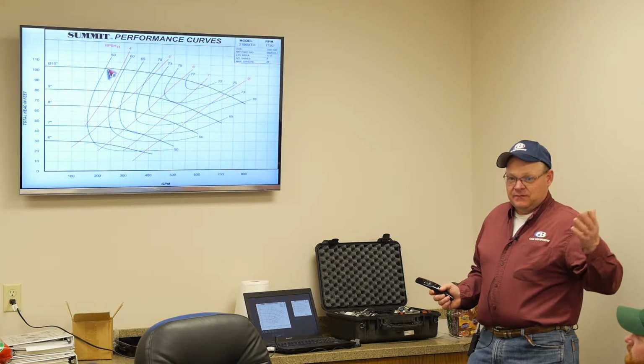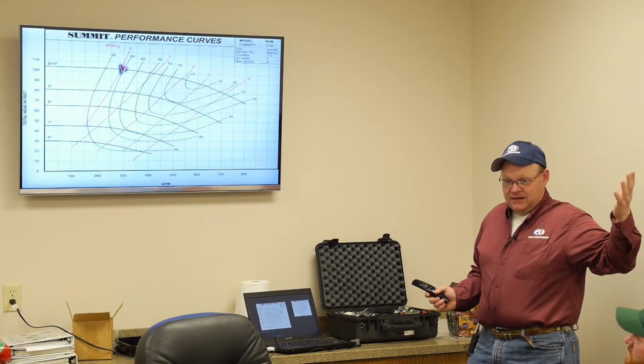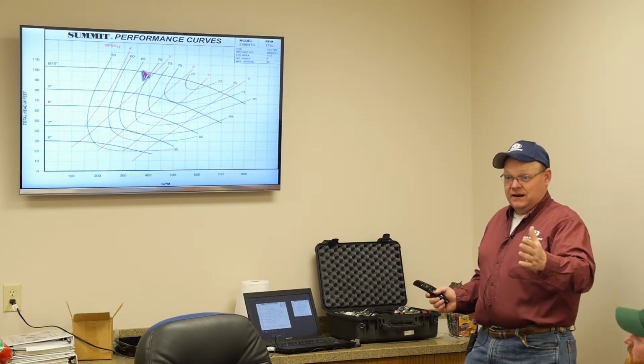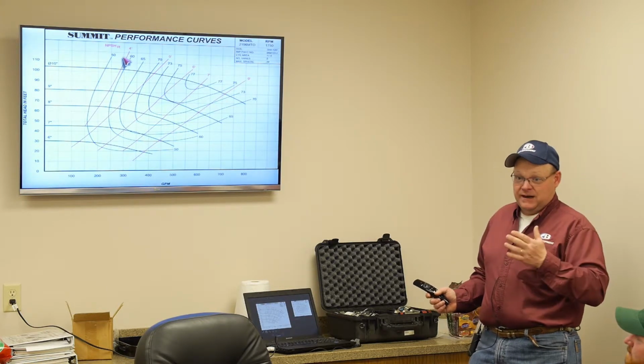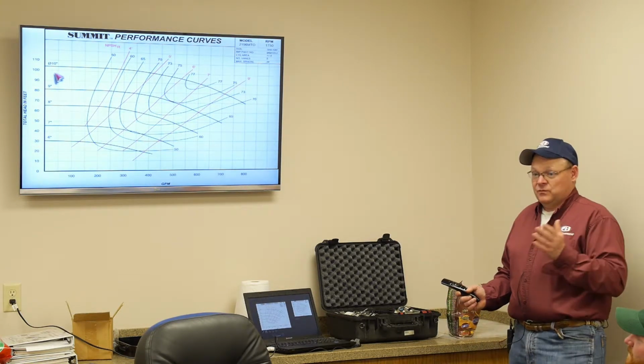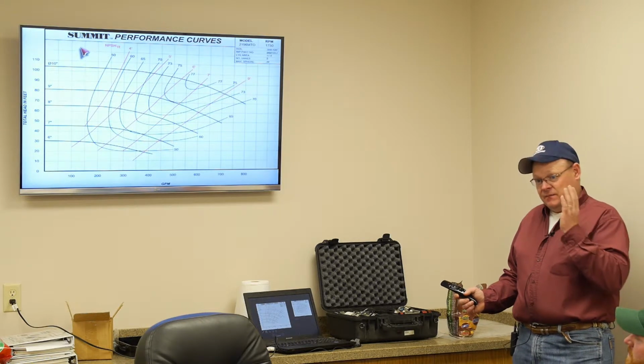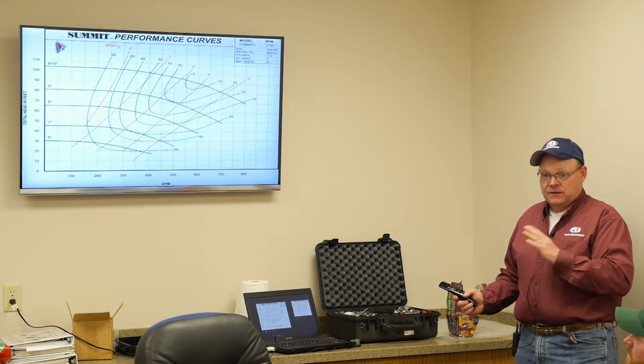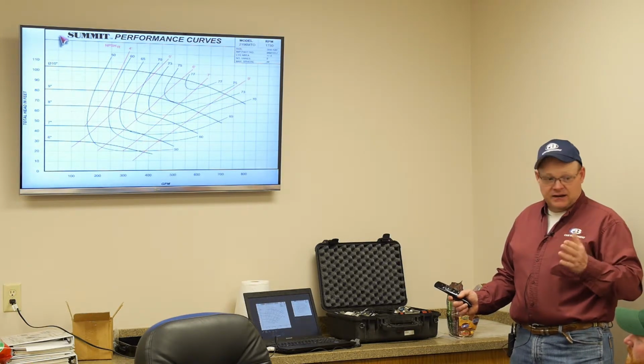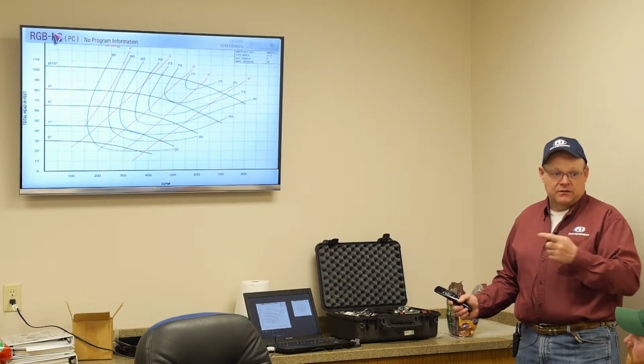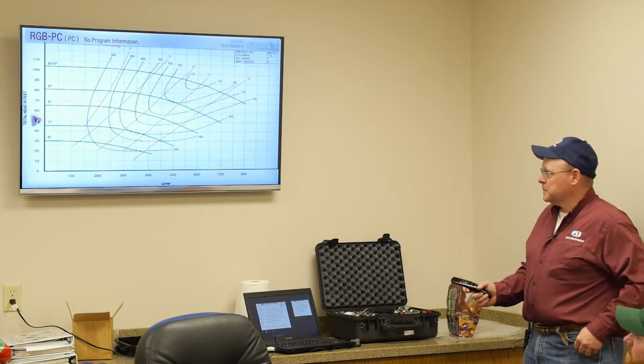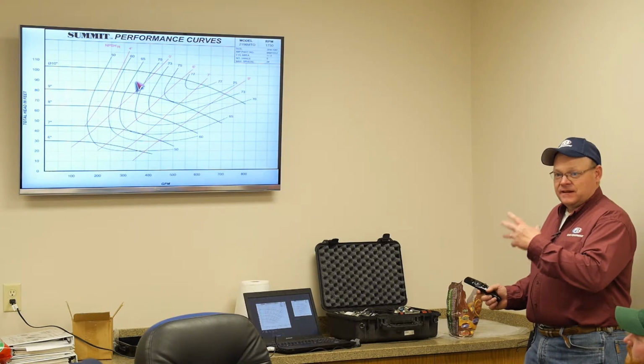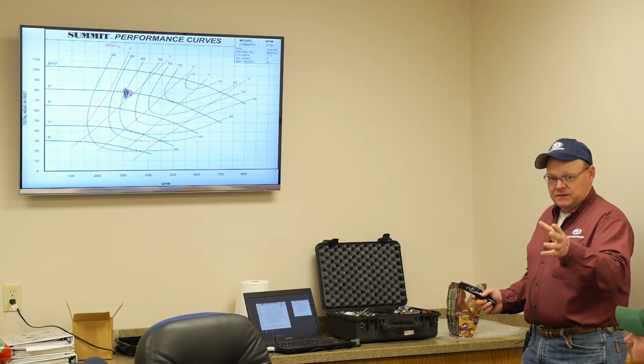Whereas we're dealing in PD pumps, we don't care. It's a flow creating device. All we got to do is get it from point A to point B. So that is why we don't care in positive displacement pumps what the pressure is. We're going to get it there. Theoretically, if we got enough horsepower, we can put it on the moon. Does that make sense? Because we have so much internal slip in the pump, we have to correct it for the specific gravity.